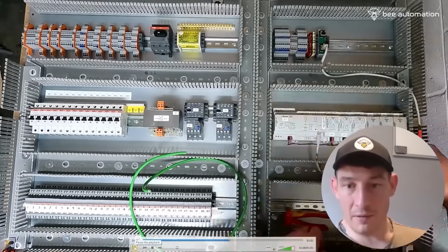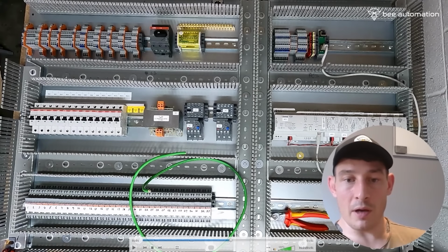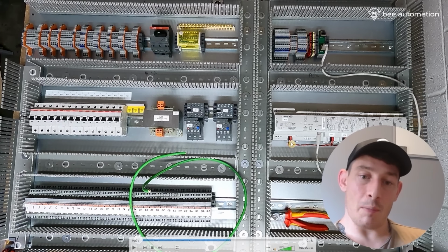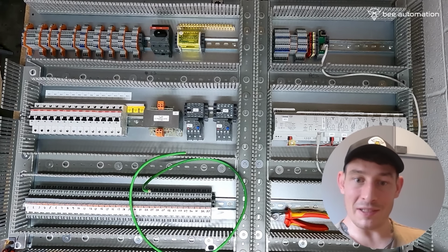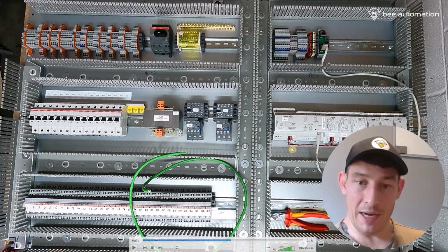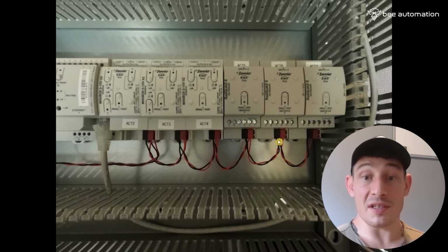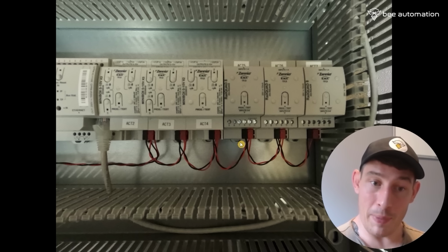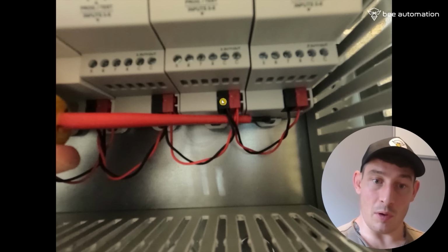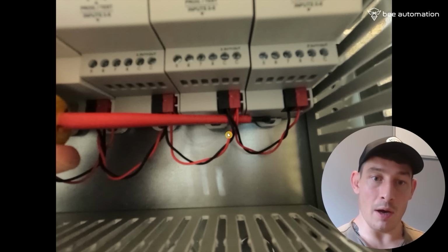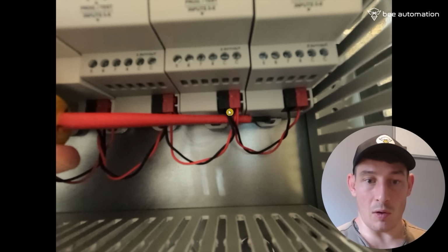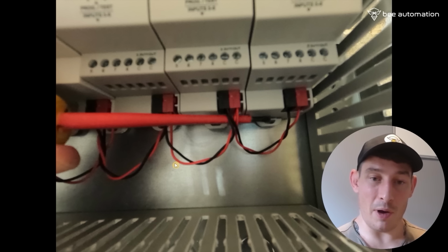This bit here with the screwdriver, I'm making sure there's not a sharp right-angled 90-degree bend coming out and then swooping down. This is what they look like before I bend them down. You can see I'm making sure that bend is a nice curved radius rather than a hard 90-degree angle, since this is solid core cable, so there's a higher chance it could snap over time.